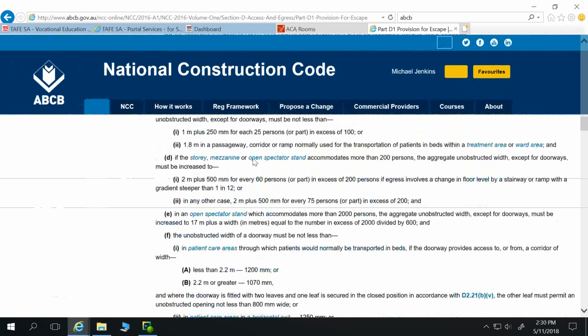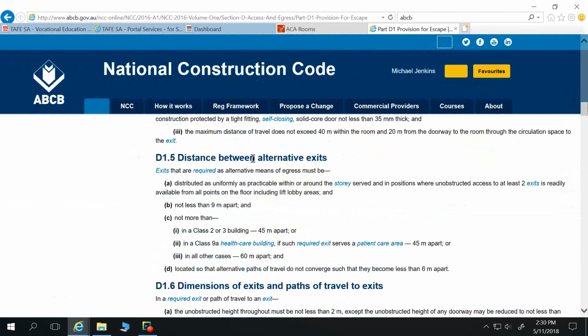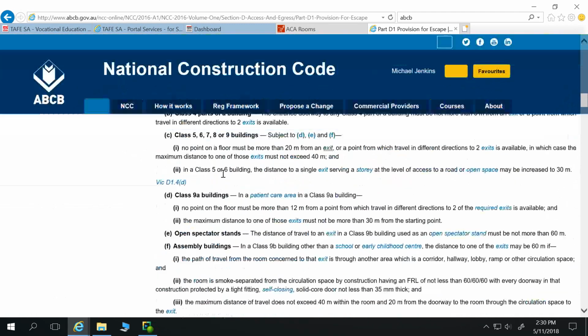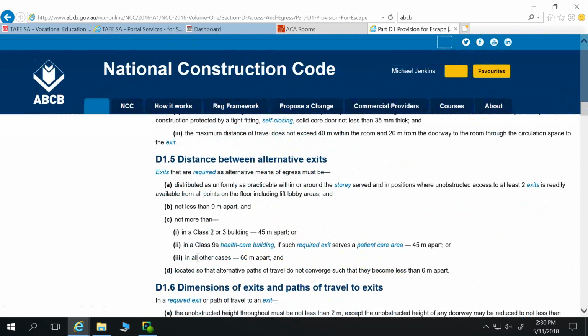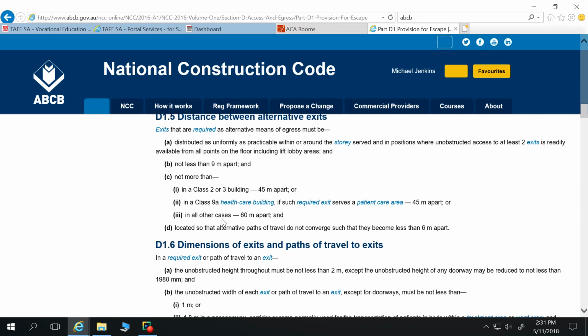And actually I had D1.5 to look at as well. Yeah. Where, okay. Exits that are required as alternative means of egress must be distributed as uniformly as practicable within or around the story served and in positions where unobstructed access to at least 2 exits is readily available from all points of the floor, including lift lobby areas. So we're not class 2 or 3, or not class 9, so in all other cases 60 metres apart.